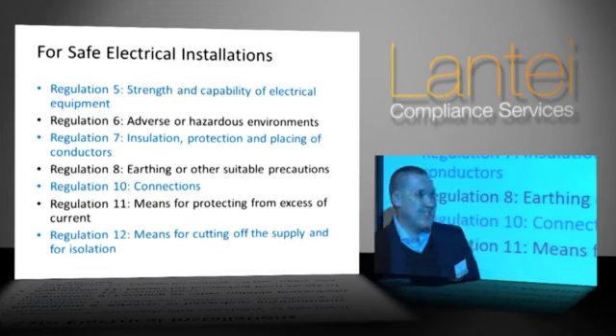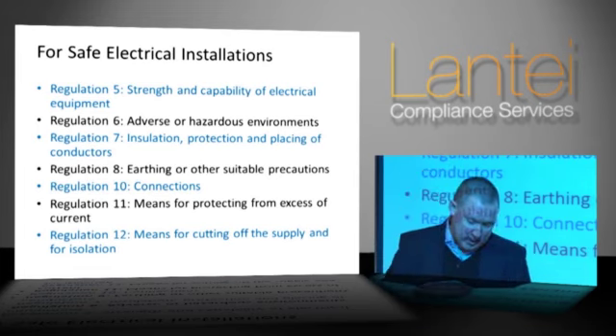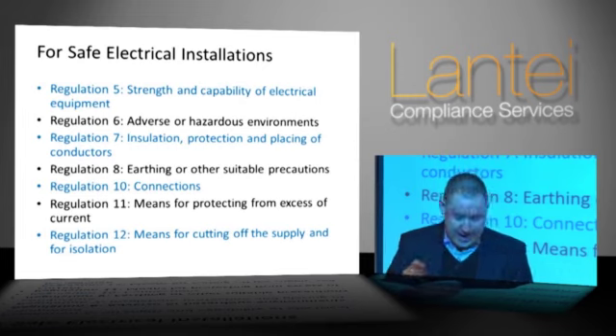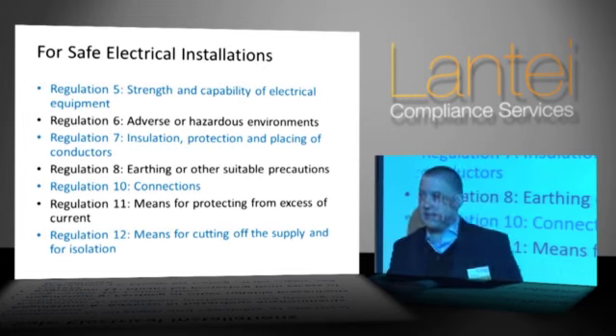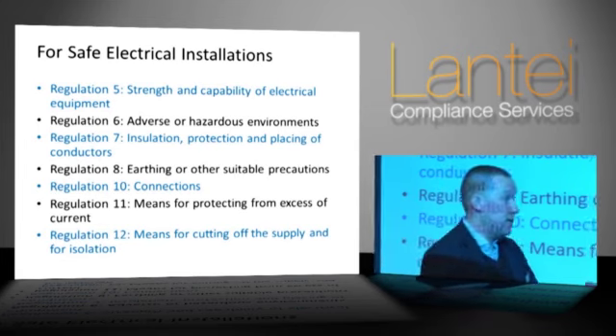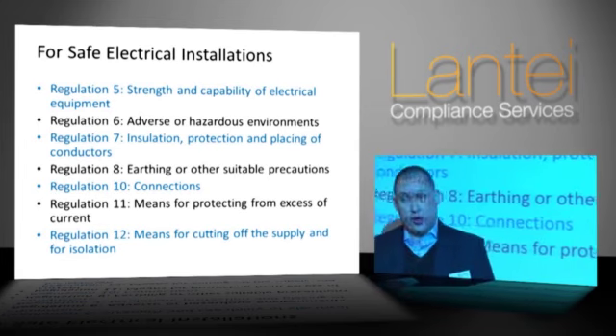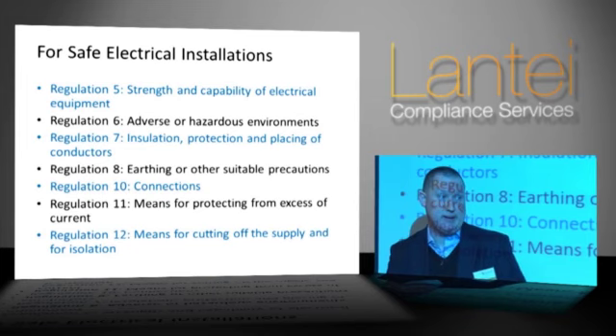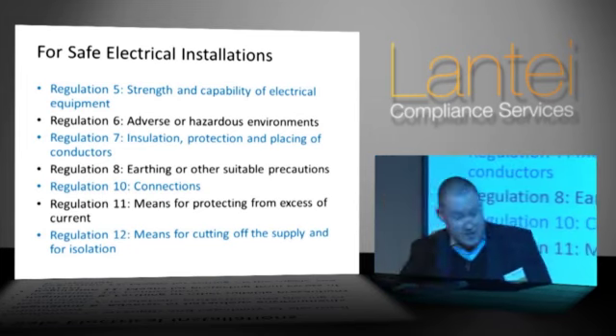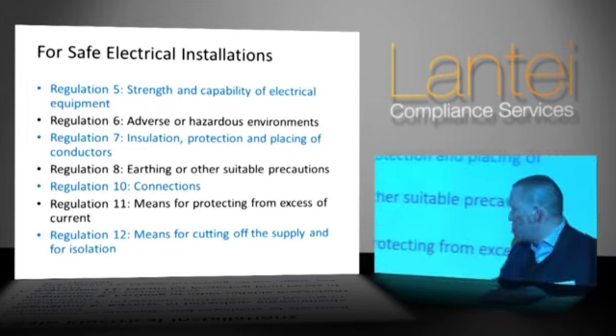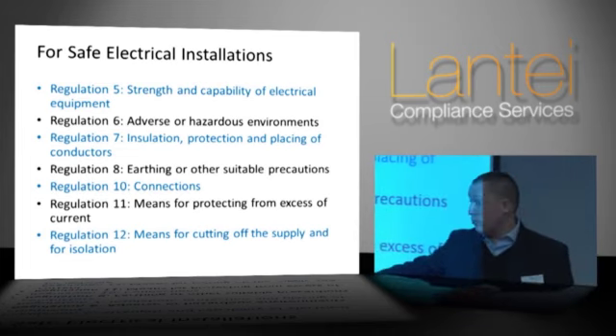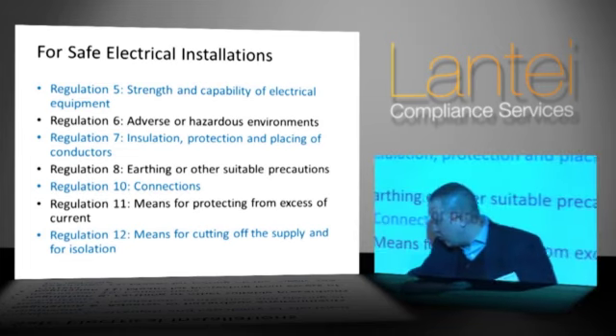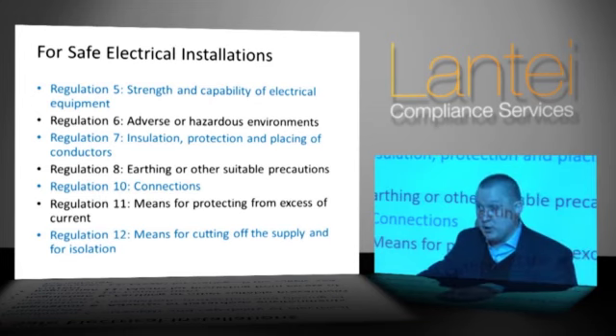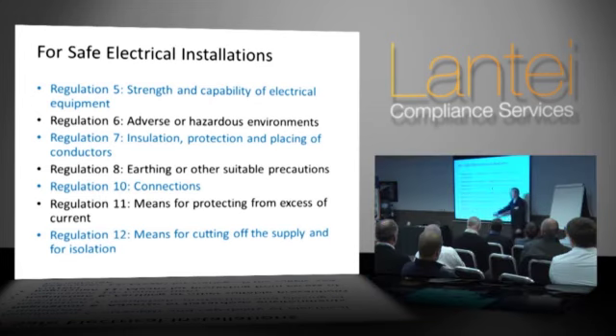Now, the term isolation has a definition, which is this: that it can be switched off, an inadvertent reconnection prevented, to enable compliance with Regulation 13, which is precautions to work on equipment made dead. I know that's a bit of a mouthful, but basically what we're saying, folks, is that we've got to be able to switch the supply off to something, and then we've got to be able to prevent it coming back on until we want it to come back on. They are basically your fundamental key requirements for electrical installations, electrical systems.